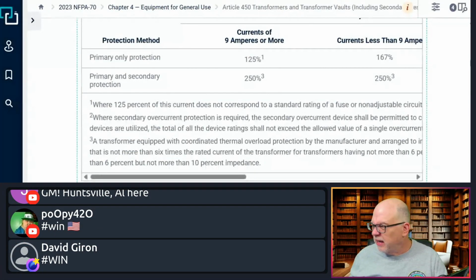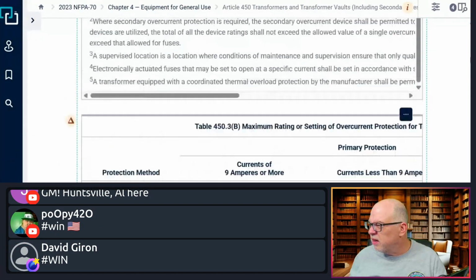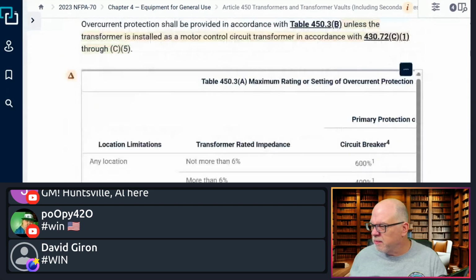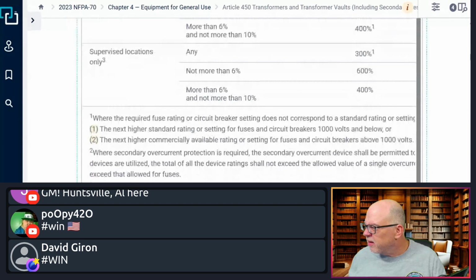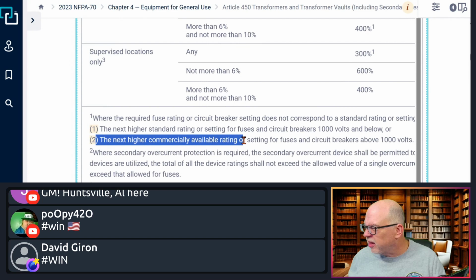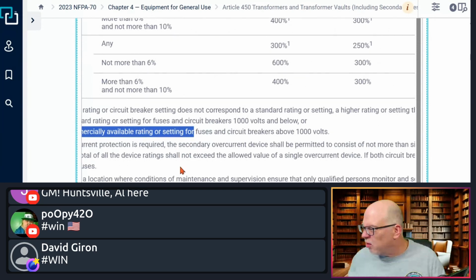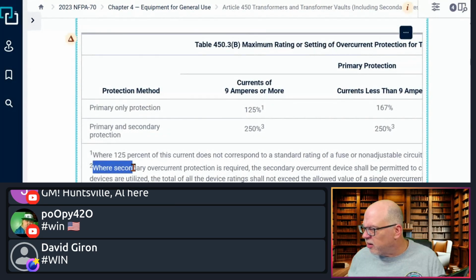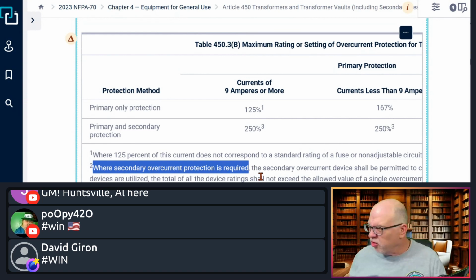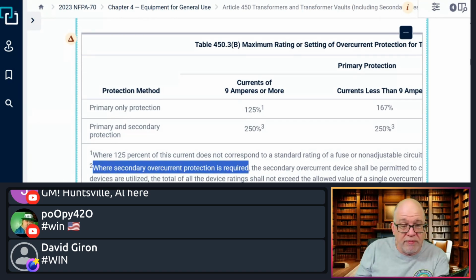And we're over here in the code. Let's see here. Let's go into, oops, back up here, right here. I don't know if you can see this or not, but it says the next higher commercially available rating or setting for fuses and circuit breakers above 1,000. I think I'm in the wrong one. Hold on. Right here. Sorry. Right here. It says where the secondary overcurrent protection is required. So in this case, where would it be required? Well, one of the examples where it may be required is where I'm using the 250% for the primary, then I'm automatically required to have the secondary protection of that transformer, right?